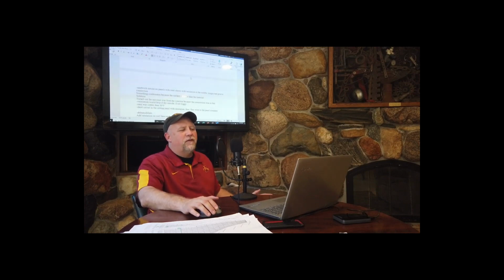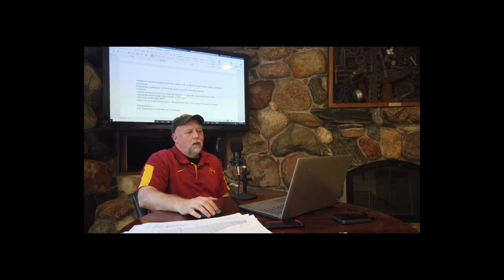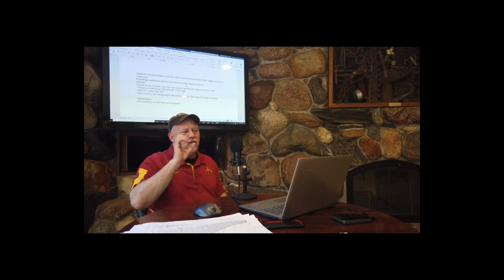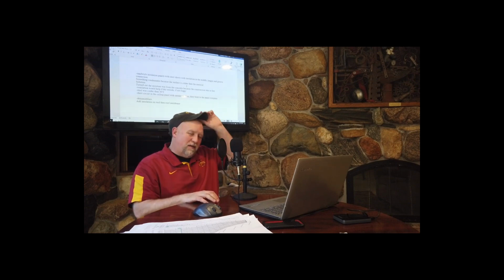Now, what's the answer? Well, they didn't have any ventilation in this building. It wasn't required. No ventilation, no drier air being brought in. The moisture that's in the building is trapped. It's trying to get out. So a little bit of ventilation could have helped. Also, if at those bar joists they would have had a little bit better of an assembly, they wouldn't have had a thermal short circuit right there at those bar joists that caused the bar joist to be a little bit colder than the rest of the building.